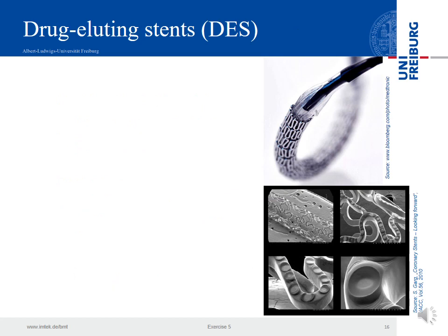So one measure that has been taken is the idea of drug-eluting stents. That means you make structures on the surface of a bare metal stent and put a polymer and hide a drug in the polymer, so that the drug is released just by diffusion and interacts with the foreign body reaction, and in the ideal case diminishes and reduces that.